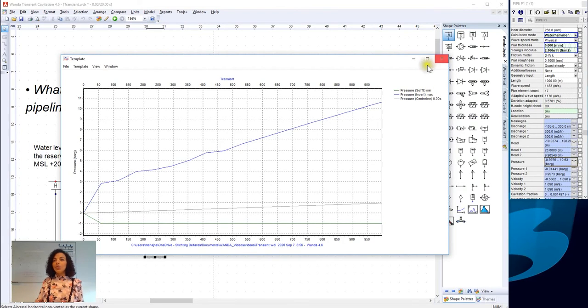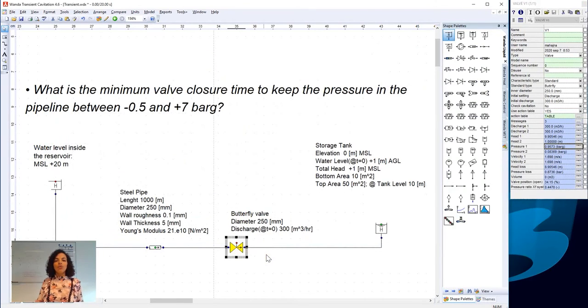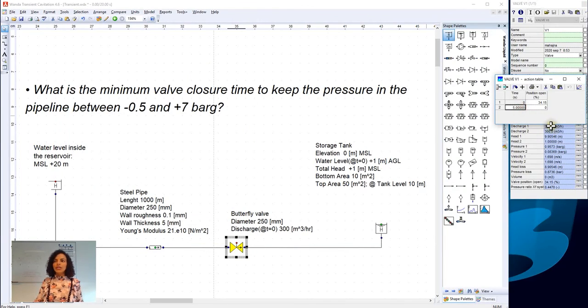Thus, we update the closure of the valve in the system. So, we go back to the action table again. And we increase the time of closure of the valve. By gradually closing the valve in the system, we decrease the pressure wave generated in the system.